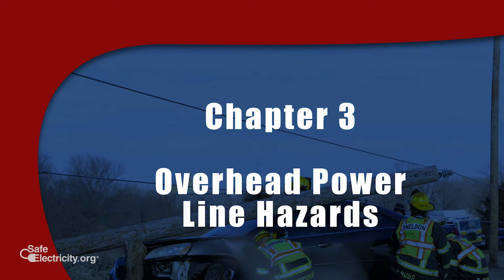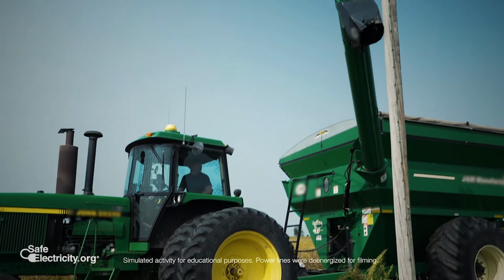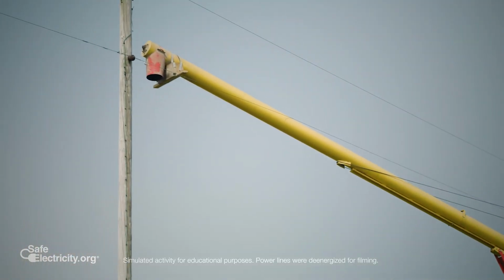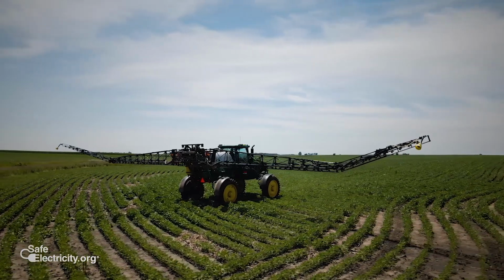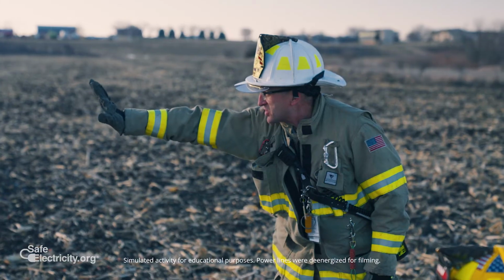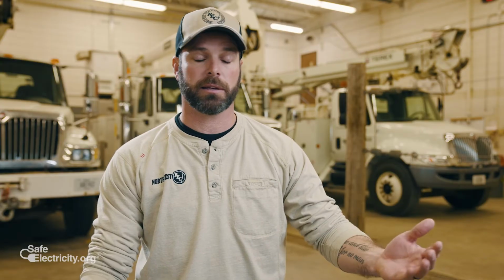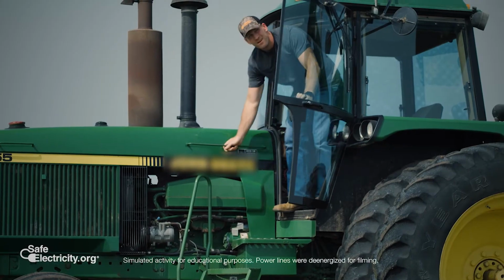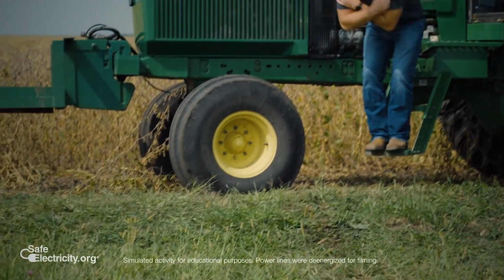Being a first responder coming on scene with large equipment—boom sprayers, cranes, excavators, and the like—do not approach the equipment until notified by the utility provider that the power is off and it's safe to do so. When the boom is in the power lines, whether it's a sprayer or excavator, just because that equipment is touching the ground does not mean the power line is off. If you go up to that piece of equipment, you're likely to create a path to ground and be electrocuted. If the operator is in there and fine, tell him to remain inside until notified he can get out when the power company shows up. If he's panicking or there's a fire, instruct him to hop off the equipment and hop away through that step potential gradient a minimum of 50 feet, if not further. Do not make the scene worse by approaching to help and becoming a victim of electrical contact yourself.